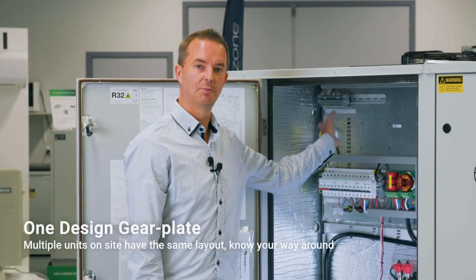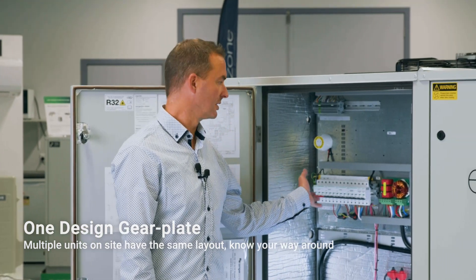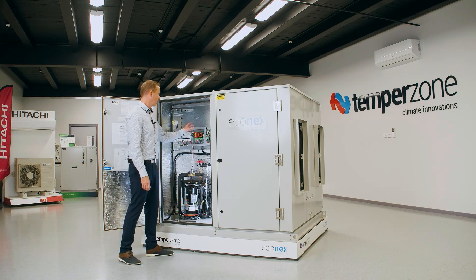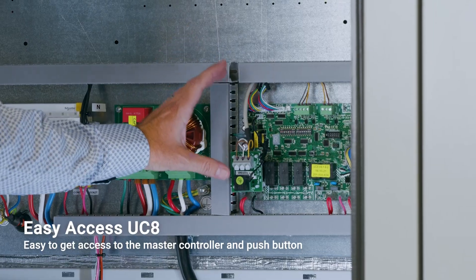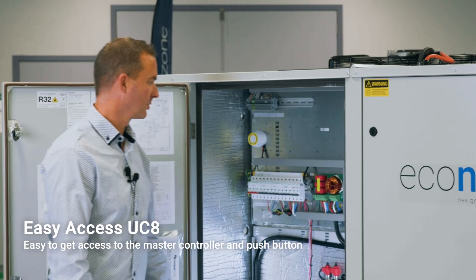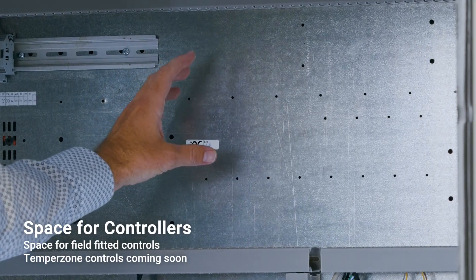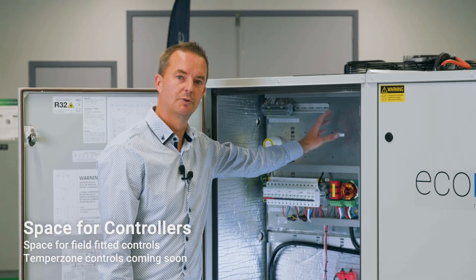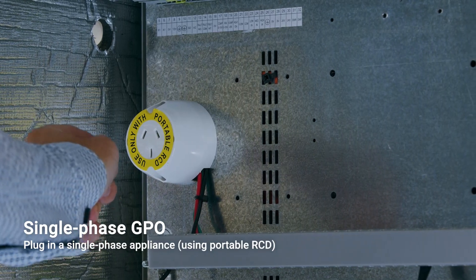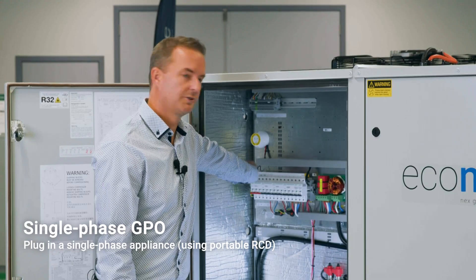We have incorporated a one-design gear plate. If you have multiple units on site, when you come up to any one of those units, the gear plate layout will be the same. We have also made the UC8 in one easy-to-access location, with push-button easy access to adjust the controller programming. We have space here for aftermarket controllers, and Temperzone will be releasing more control platforms later in the year. We have a socket here for a portable RCD so you can plug in any appliance you need on site to do any servicing.